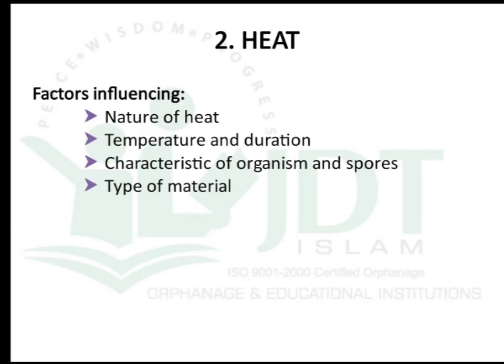Factors affecting heat sterilization include: nature of heat — moist heat is more efficient than dry heat; temperature and duration — as temperature increases, the duration of sterilization can be decreased; characteristics of the organism and spore — some spore-forming microorganisms require higher temperatures for destruction; and type of material — only heat-stable materials should be selected for heat sterilization.